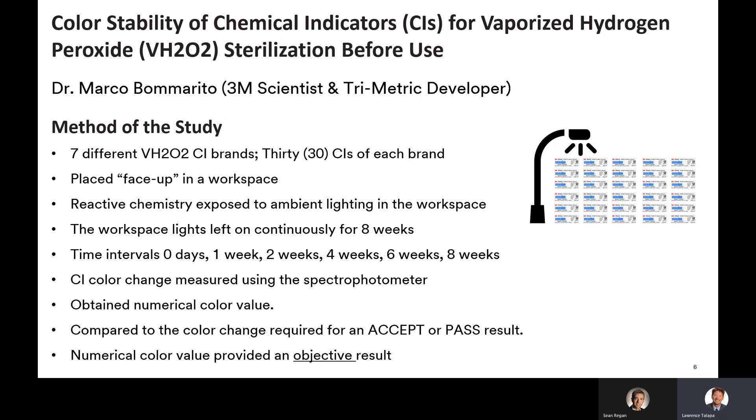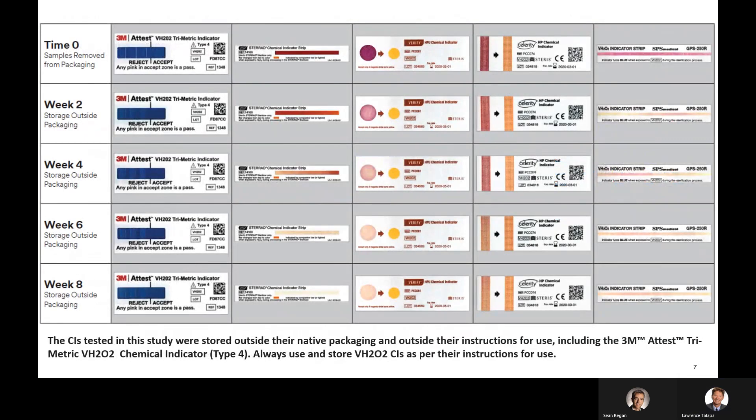The CI color change was measured using a spectrophotometer. By using a spectrophotometer, Dr. Bommarito obtained a numerical color value on the CI color change. A numerical color value provides an objective result for the evaluation of each CI in the study. The color results for each indicator using the spectrophotometer were compared to the color change required for a pass result. This numerical data is summarized in the 3M study.